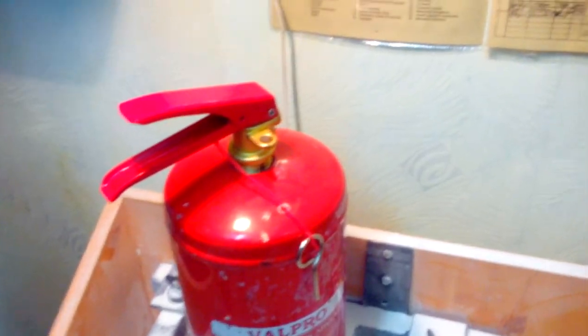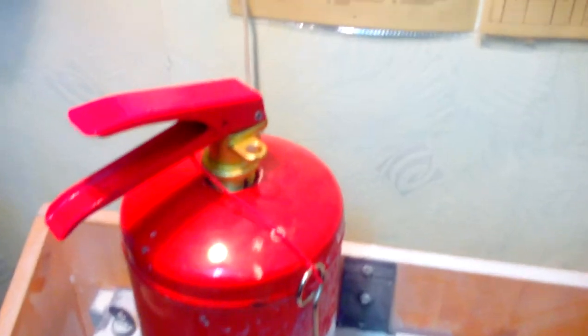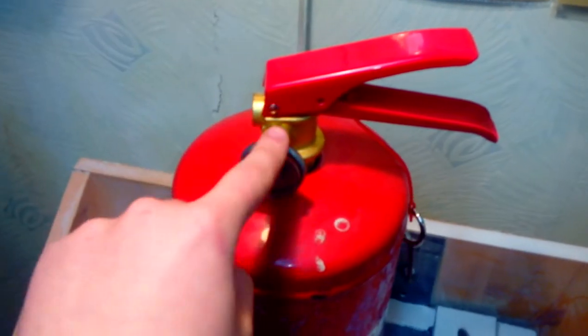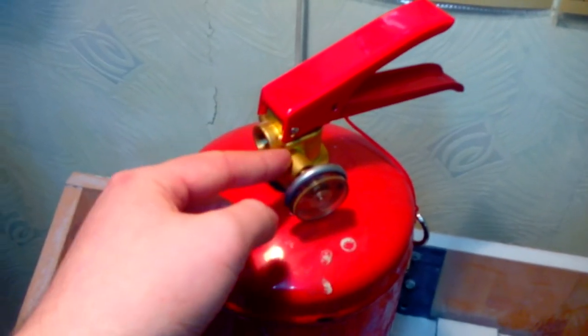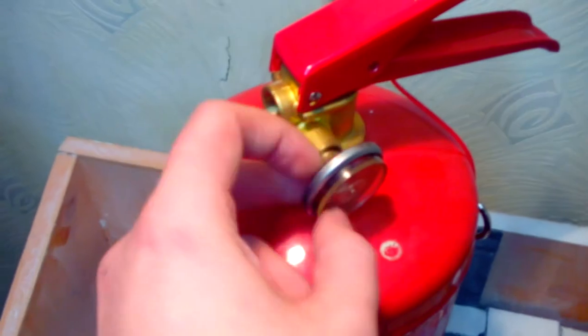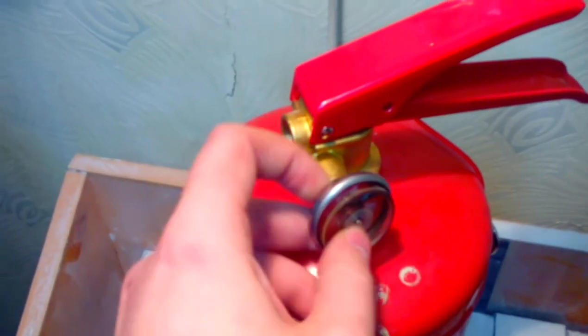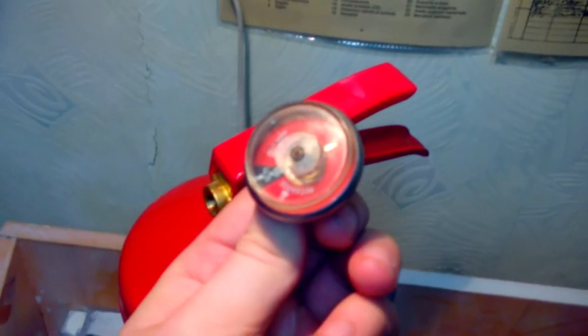And you can't check it by weight. I mean, it weighs like a normal fire extinguisher, because it hasn't been discharged in the matter of actually discharging it. They broke the seal by dropping something on this thing, and then the pressure inside slowly vented itself out, because this doubles as an emergency vent. So obviously I already had this thing disassembled. This is why I can just open this off so easily. I am going to keep this, just to show clients what happens if you don't change these things.